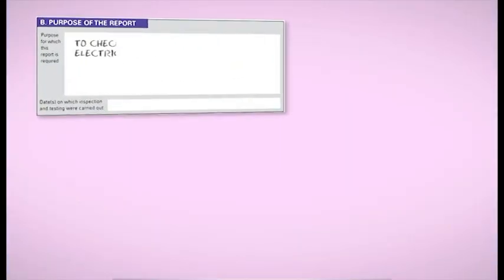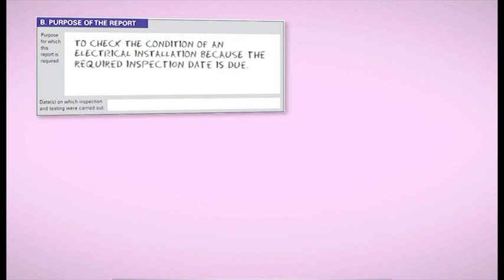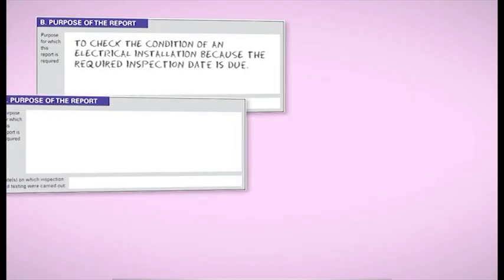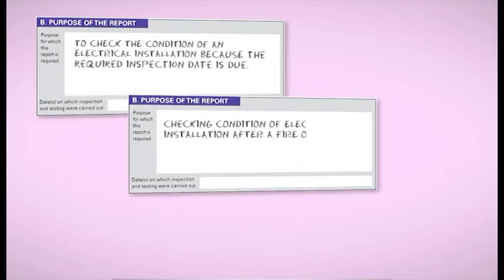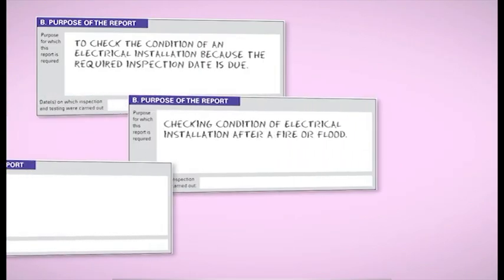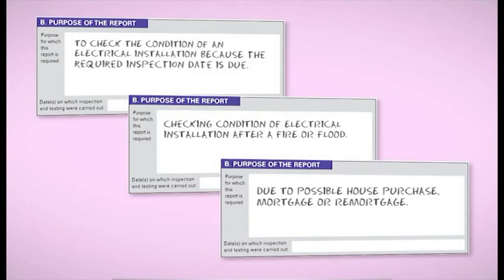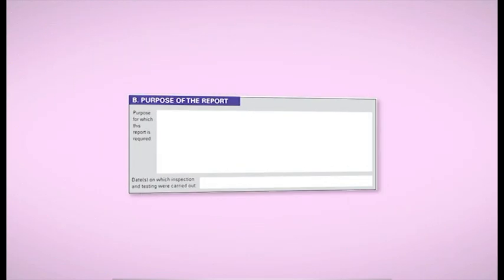Now, I've seen all sorts of stuff written in here. A particular favourite was to check the condition of the electrical installation. Now, if they'd added the words "because the required next inspection date on the electrical installation certificate was due," this would have been fine. You could also have checking condition of electrical installation after a fire or flood, or due to possible house purchase, mortgage or remortgage, as long as the reason is clearly understood.